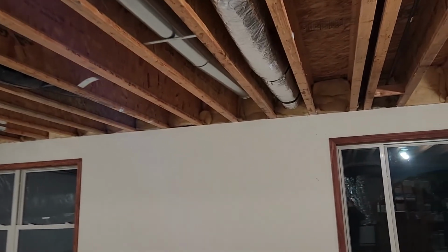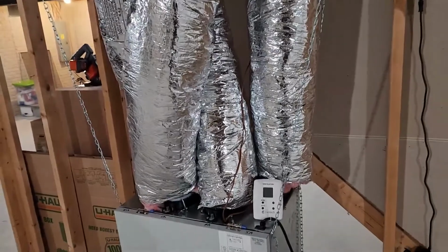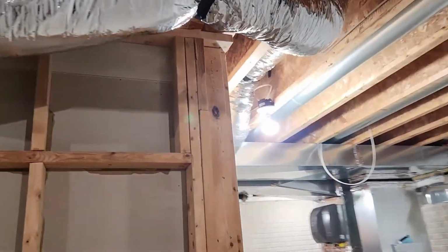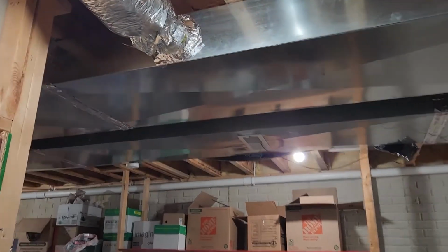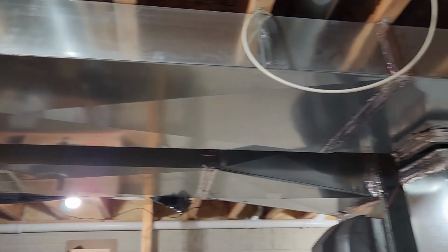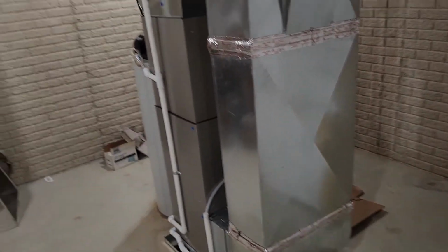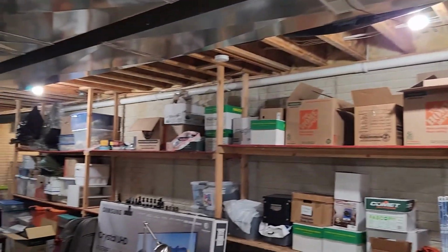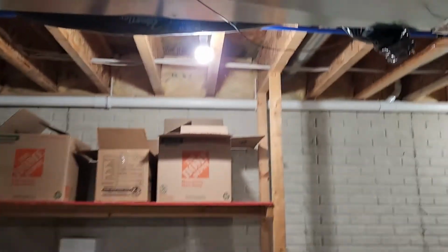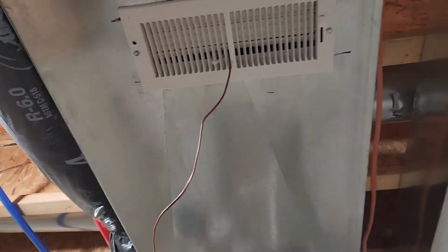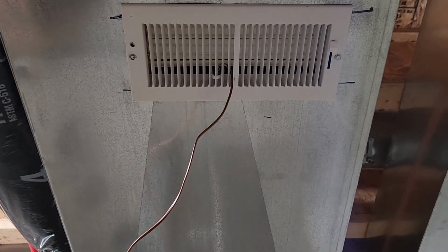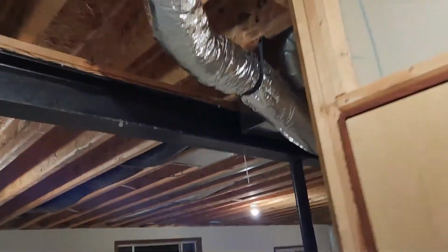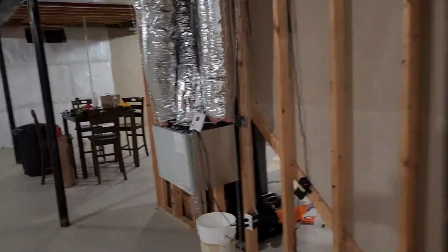And then we've got our outdoor air that comes in and goes into the ERV. Then that treated outdoor air comes out as supply air, and makes its way to the furnace return over here. Of course, that fresh supply air is then pulled down through your furnace blower and circulated out the supply side of the furnace and distributed throughout the house. Here is that sail switch I was describing to you guys earlier. It's in the duct and detects anytime the furnace blower comes on, and then that thermostat wire is run all the way back to the control panel of the ERV.